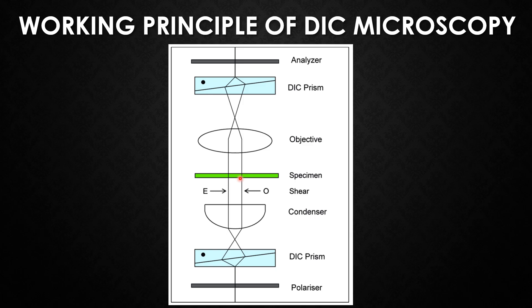Next, the two wavefronts pass through the specimen and are retarded to varying extents within the specimen. The light then enters the second DIC prism through the objective, and the setup recombines the wavefronts. If there has been a phase shift between the two rays as they pass through areas of different refractive index, then elliptically polarized light is the result. Finally, the light enters a second polarizing filter termed the analyzer. The initial polarizer and this analyzer form crossed polars. The analyzer permits the passage of some of the elliptically polarized light to form the final image, and all remaining light is blocked by the analyzer. This is the working principle of DIC Microscopy.